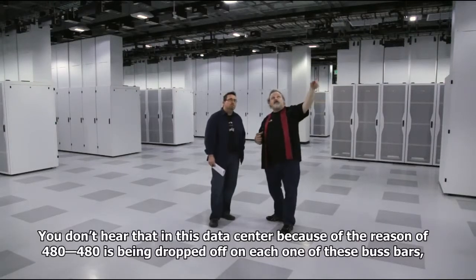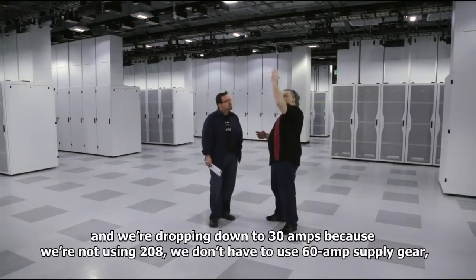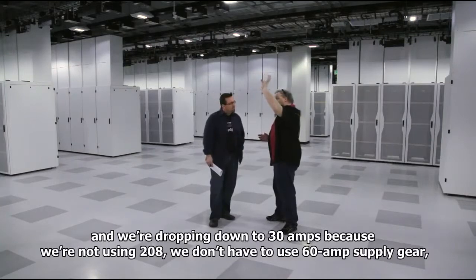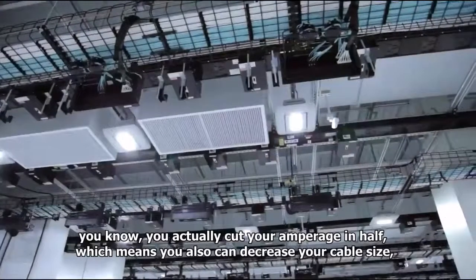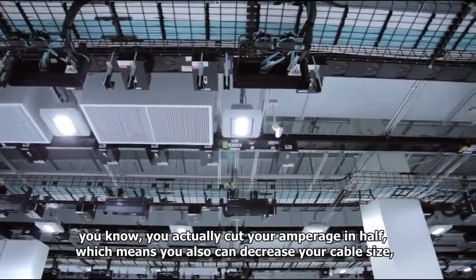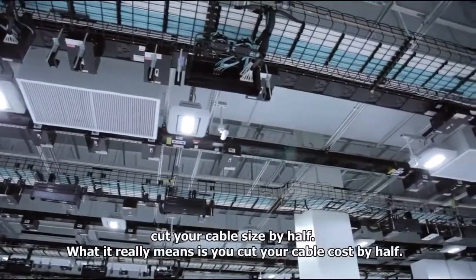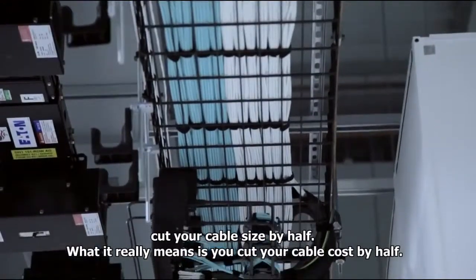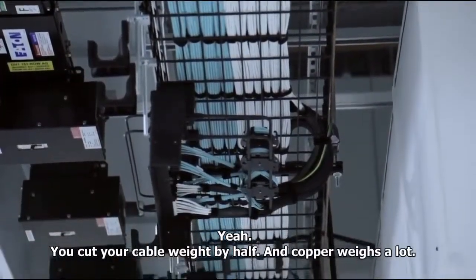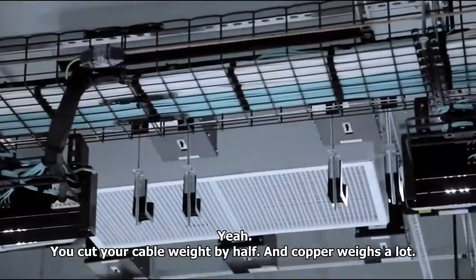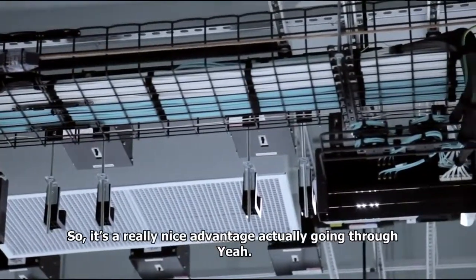480 is dropped off on each one of these bus bars, and we're stepping down to 30 amps because we're not using 208 and don't have to use 60 amp supply gear. You actually cut your amperage in half, which means you can also decrease your cable size. Cutting your cable size in half really means you cut your cable cost in half, and you cut your cable weight in half—copper weighs a lot. It's a really nice advantage.